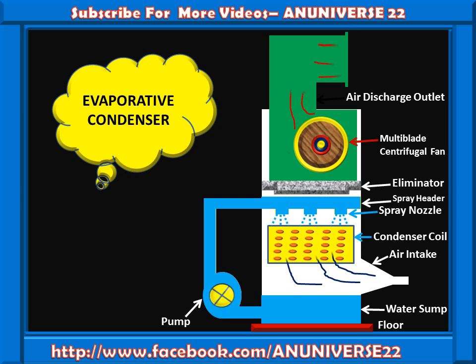But most troublesome point about the evaporative condenser is the difficulty in keeping the surface of condenser coil clean. The condenser coil being both hot and wet in operation, the dirt carried along with the air stream forms a hard layer on the condenser. Scale also forms a hard layer if hard water is used. Once these hard layer forms, it is never possible to effectively clean the coil, so the capacity of condenser gets substantially affected, and because of this maintenance problem, evaporative condenser are not much in favor.